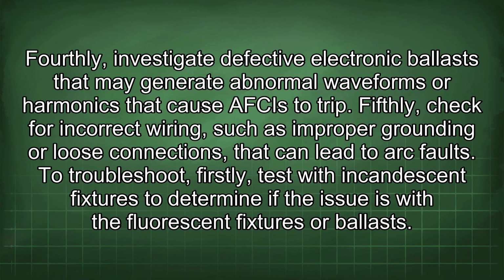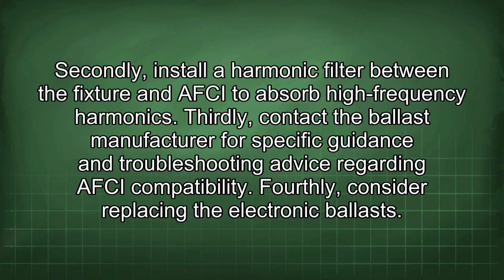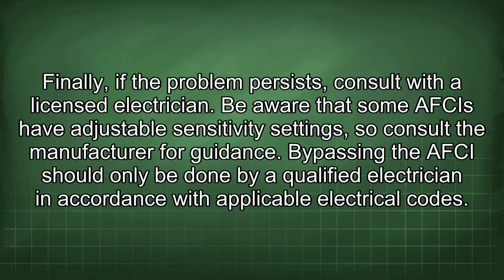To troubleshoot, firstly, test with incandescent fixtures to determine if the issue is with the fluorescent fixtures or ballasts. Secondly, install a harmonic filter between the fixture and AFCI to absorb high-frequency harmonics. Thirdly, contact the ballast manufacturer for specific guidance and troubleshooting advice regarding AFCI compatibility. Fourthly, consider replacing the electronic ballasts. Finally, if the problem persists, consult with a licensed electrician. Be aware that some AFCIs have adjustable sensitivity settings, so consult the manufacturer for guidance. Bypassing the AFCI should only be done by a qualified electrician in accordance with applicable electrical codes.